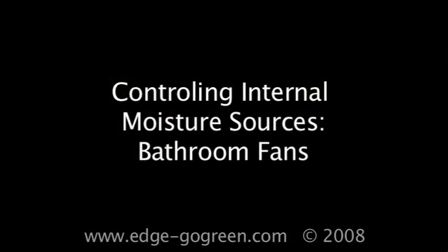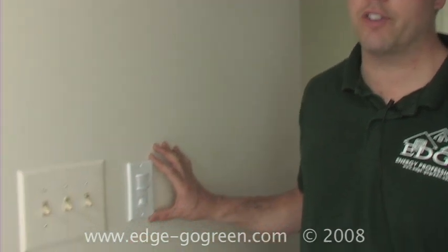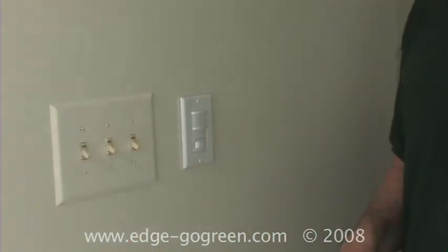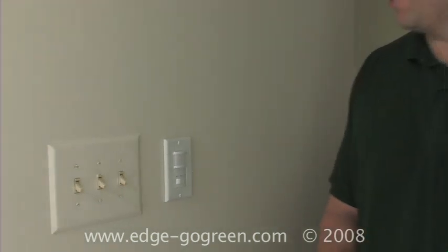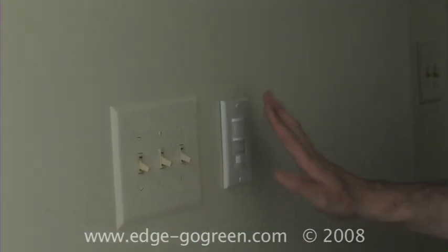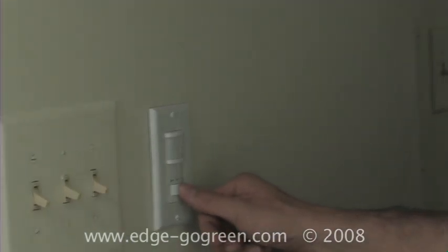With overly tight building shells, or if we're recommending to you to over tighten your house, but then to provide back mechanical ventilation, bathroom fans and the source control of moisture are two of the most important things for you to focus on. A very easy way to do that is to make sure that the bathroom fans are being run all the time or when they need to be run. There's a couple of different strategies in order to do this. The one that I think is the cheapest and the easiest to retrofit is to put a $15 to $20 timer/motion sensor control on your bathroom fan switches, so that every time this fan is left in auto, you walk by this motion sensor switch, the fan itself comes on, it stays on for 20 minutes, and you've left that room and you don't have to ever worry about turning your bathroom fan off or on again.